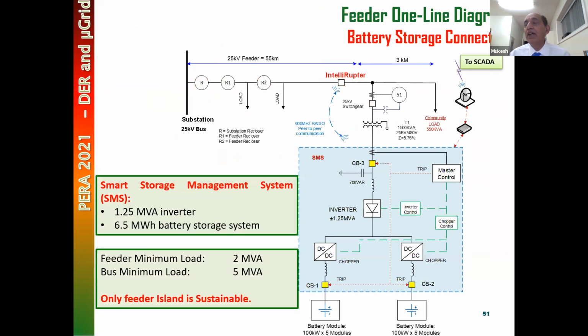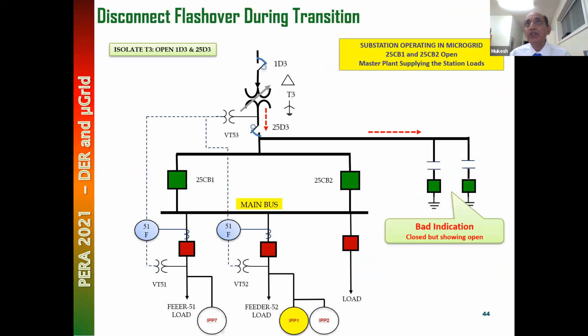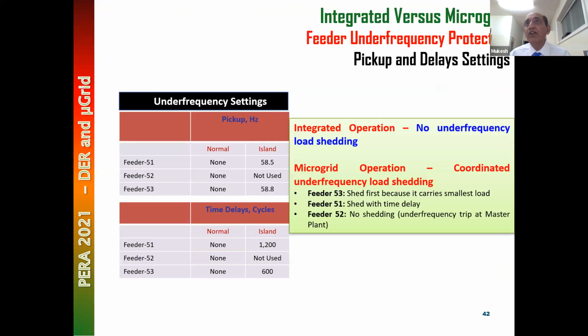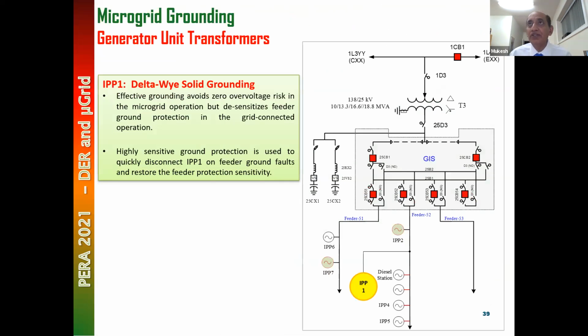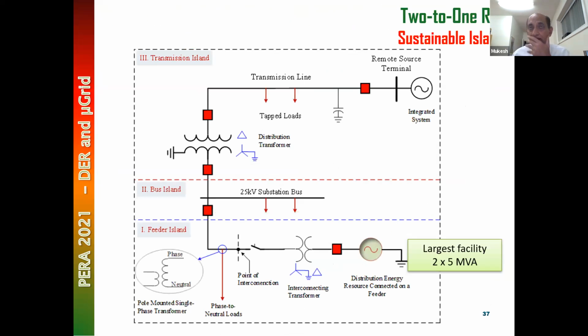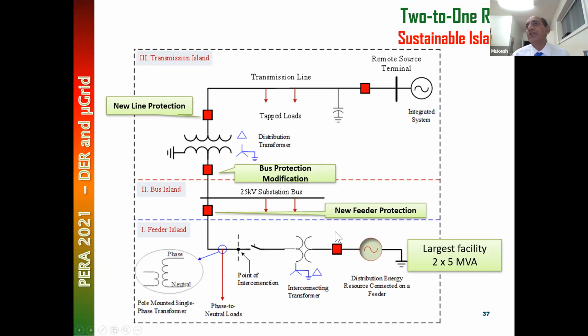In a microgrid, if this is a cable, it will have a lot of capacitance. And this source, a weak source, is an inductive weak source. Conventional generators are inductive sources. They have inductive impedance. This inductive impedance of a weak source can form a resonance circuit with the capacitance. It can form a near 60 Hz resonance, and that can cause a problem during faults in a microgrid situation. However, when you have inverter-based resources, they are not inductive, so the resonance problem is not there.